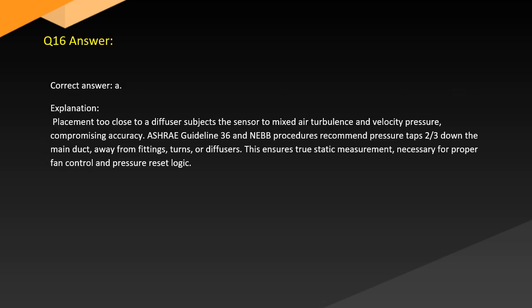Answer. Correct answer: A. Explanation. Placement too close to a diffuser subjects the sensor to mixed air turbulence and velocity pressure, compromising accuracy. ASHRAE Guideline 36 and NEBB procedures recommend pressure taps two-thirds down the main duct, away from fittings, turns, or diffusers. This ensures true static measurement necessary for proper fan control and pressure reset logic.